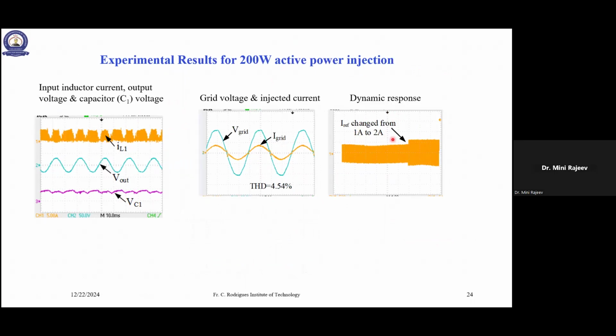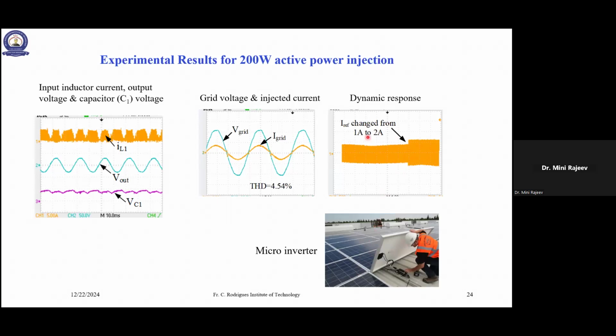And then this is the dynamic response. If I change the reference, the output changes. This shows that if the PV panel reference is changed, the output will change. This is a 200 watt power level inverter, so we can use it as a micro inverter. Micro inverter means one which is fitted behind the PV panel itself.